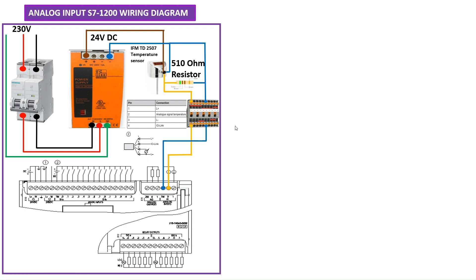In this example, we're going to use the IFM temperature sensor, model number TD2507, and connect it to an S7-1200 PLC analog input. This is how you need to do the wiring. The temperature sensor has a four-point connector: pin 1 is L+, pin 2 is the output, and pin 3 is L−.